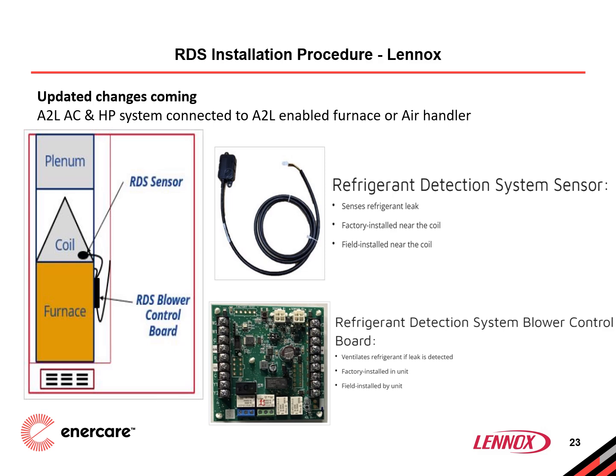Some of the key features of the Lennox RDS are proactive leak detection, which monitors the airstream for refrigerant leaks to ensure safety and compliance with A2L refrigerant standards. Secondly, automation and protection. When a leak is detected, the RDS disables the system operation, such as the burner, and activates the blower to ventilate.